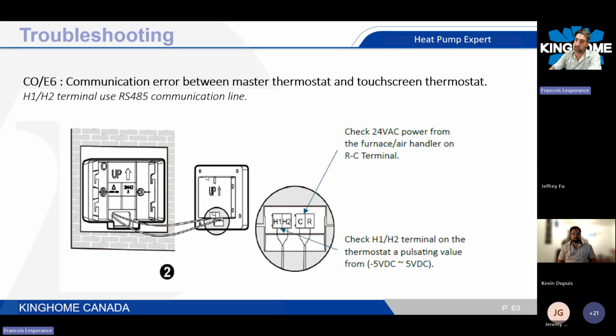You see on that picture, you have some hooks, okay? So there are some sliding portions over here. So you have to lift up and then pull the thermostat, because you have some anchors over here. They need to enter into that slide and you push it down when you install it. So when you remove it, you have to lift it up and then pull. All the connections will be directly at the back of the thermostat itself. It's not on the back plate. So you need to have enough wire to pull it out, okay?